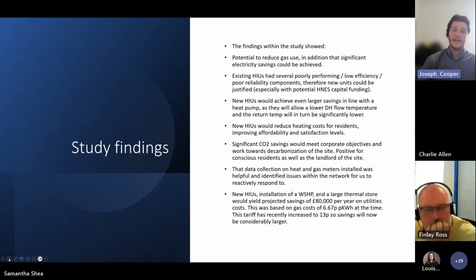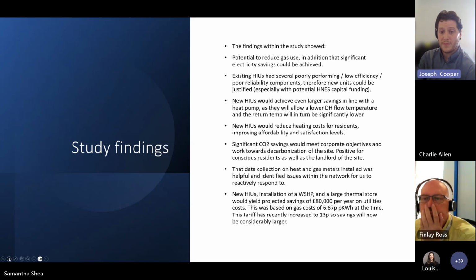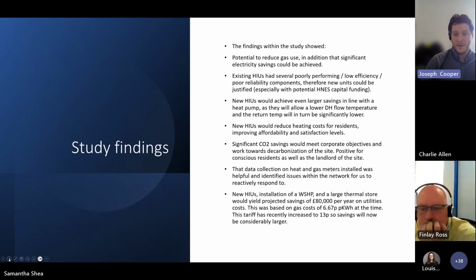Data collection on heat and gas meters installed was really helpful. It identified issues within the network for us to reactively respond to, and highlighted problem areas for us to jump on day-to-day from an operational side. It also showed that new HIUs, along with installation of a heat pump and a large thermal store, would yield projected savings of £80,000 per year on utilities costs, which is a massive saving that can be passed on to the residents as well.